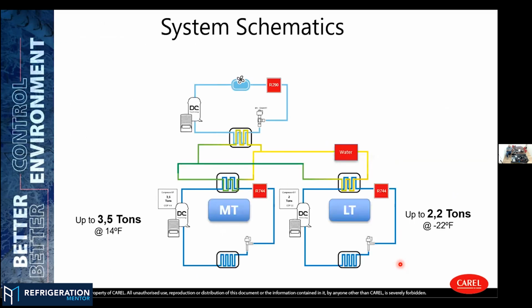I put here some examples. For example, chilled water generated by a propane chiller, to be like 100% green. And you have an MT unit that can reach up to 3.5 tons, and also a unit for low temp application that can reach 2.2 tons. So we have solutions for both medium temperature and low temperature showcases or cold rooms running in the same unit. And in this case, we just have a water loop system with chilled water that makes it run. We can integrate it into the HVAC system.